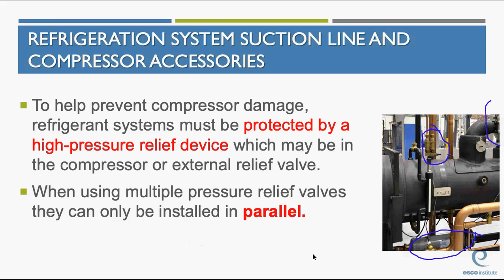How much do you think a compressor like the one on this system in the picture costs? $20,000? Easily. Okay, they're built specific to the job, and usually it involves knocking down walls or ceilings to bring the new compressor into the machine room. Okay, so this is a major issue. So if I have to let out 200 pounds of refrigerant and evacuate a building, it's much better off than having the chance of having that compressor blow out on me. Okay, so again, we protect it either internally or externally with the relief valve. Most of the hermetic compressors that you work with, that's the smaller ones that are used in commercial or light commercial refrigeration and air conditioning, that relief valve is going to be internal. Okay, it's an internal relief valve.